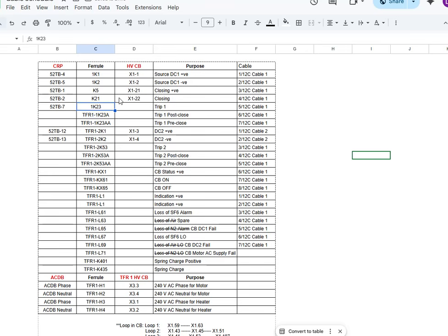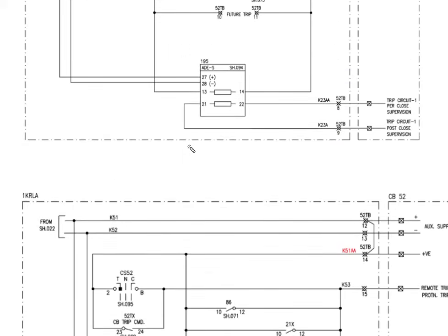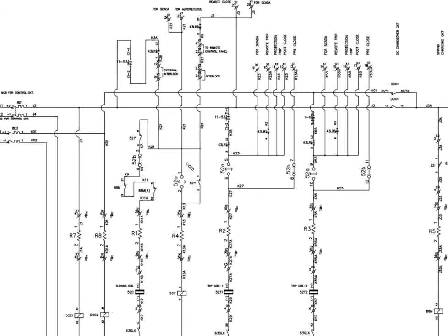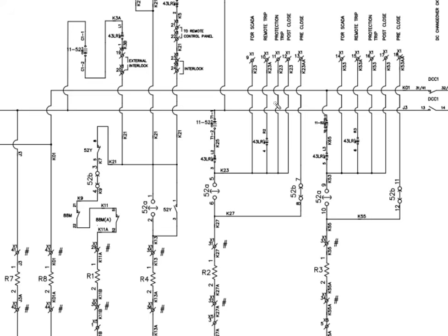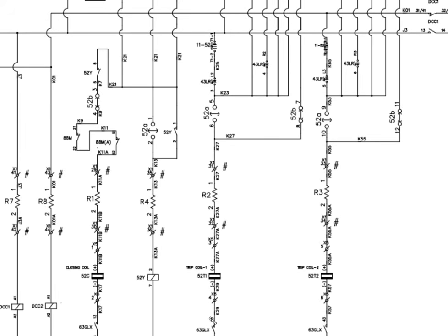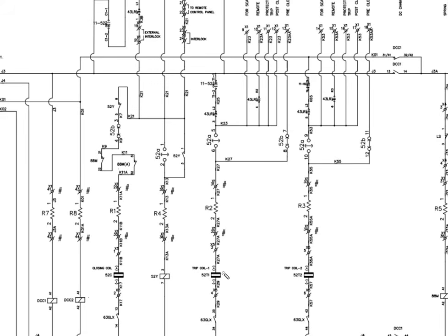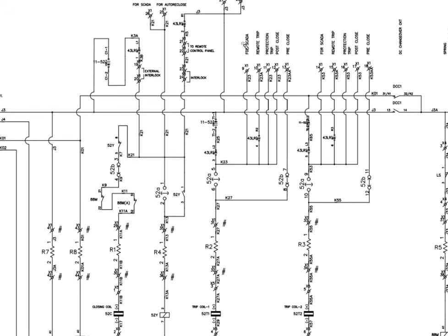Now we'll check the TB number in the circuit breaker. Okay, TC1, so we'll zoom out a bit. This is the tripping coil. Negative is being continuously given to the tripping coil, and the positive comes from the remote or SCADA for protection trip.